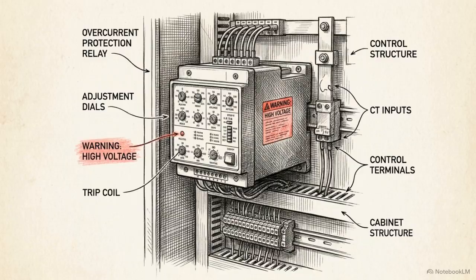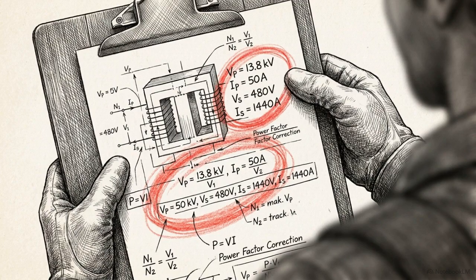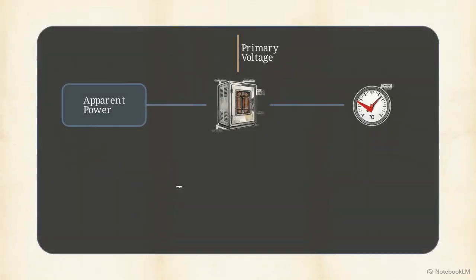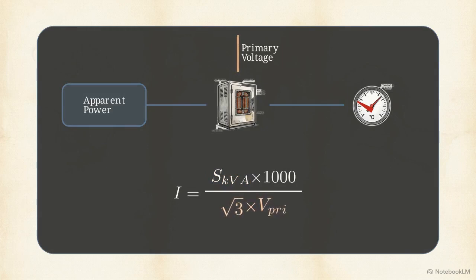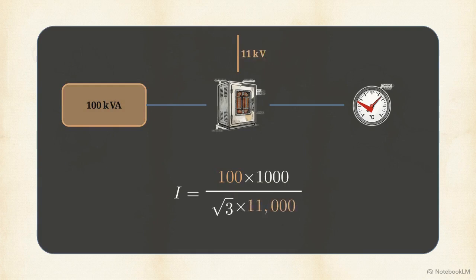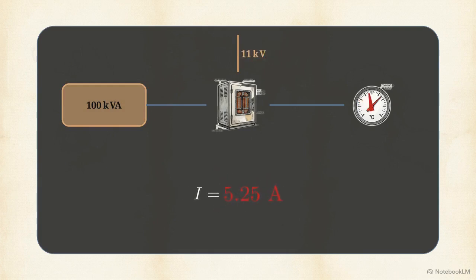Before we can set this relay, we have to calculate the transformer's full load current. This equation shows how we find that value. Rated power in kVA times 1000, divided by the square root of 3 times the rated voltage. For example, a 100 kVA transformer with an 11 kilovolt primary yields a full load current of 5.25 amps.